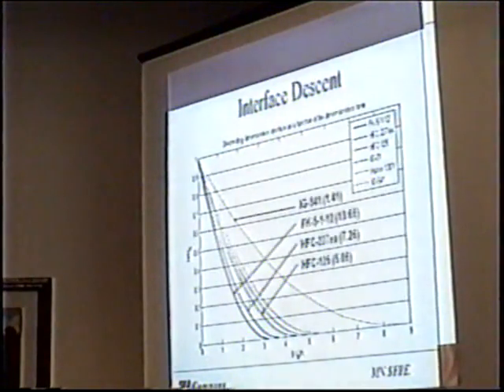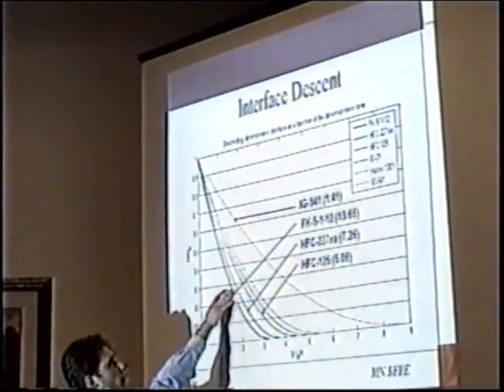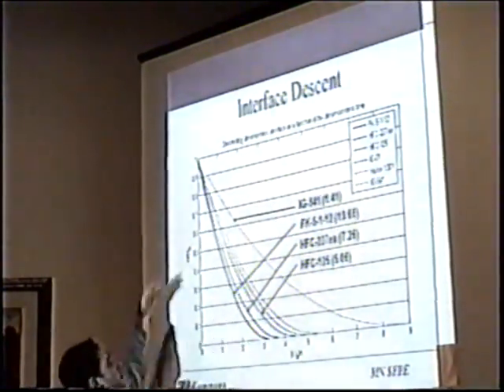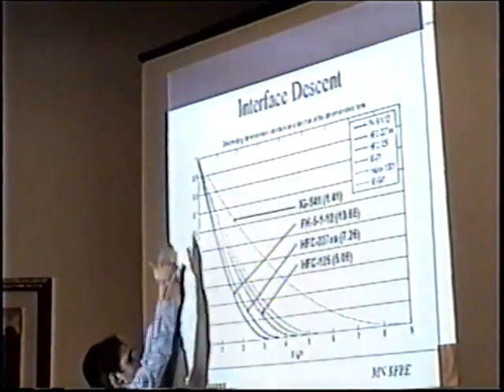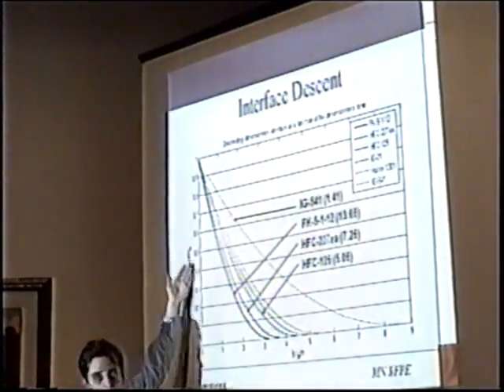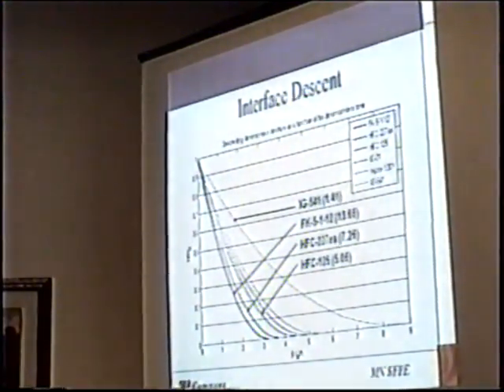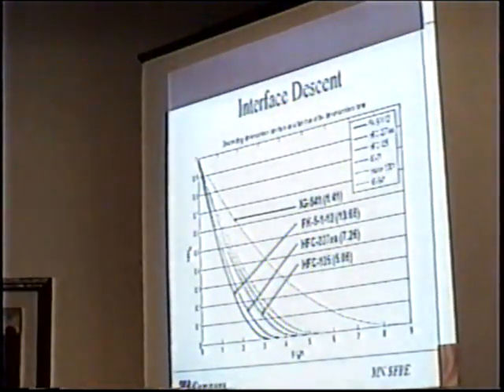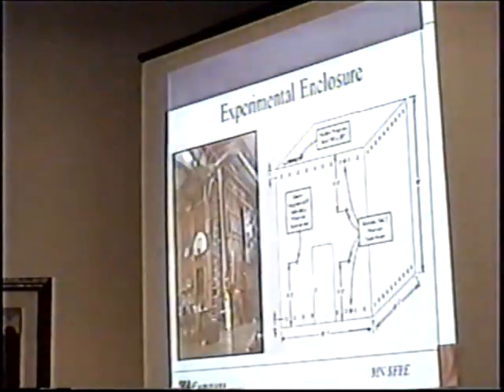So we can play around with our theory a little bit and we can see that our different agents, this would be FK-5-1-12 all the way over here. It's going to descend fastest. This is height, and this is time, essentially saying that the interface will fall with time through this height. And on the far right-hand side, IG541, you can see this agent doesn't actually have a problem with hold times. It's going to hold indefinitely. However, it does have another potential for damage to the enclosure, which is overpressurization. So there's a couple things to play with here. Of course, right now we're only looking at the hold times.